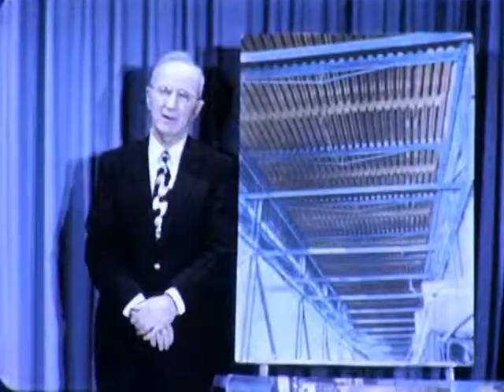Now I will show you a few examples of what happens when the protective devices are not capable of interrupting such currents. But before I do, let's review the primary functions of a protective device, or a circuit breaker as it is known. There are 2 functions. One, to open and close a power circuit under normal or abnormal system conditions. Number 2, to interrupt the maximum short circuit current which can be developed on a system, and then, if desired, be capable of being instantly reclosed to carry out its functions.